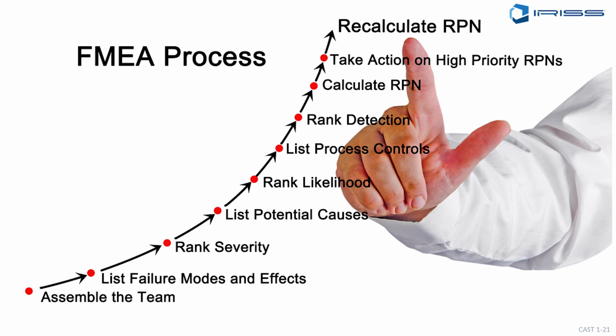What happens to my process or my facility if this asset fails? What gets affected downstream? Electrical infrastructure is a pyramid—the stuff at the top takes out everything below it. That piece of incoming medium voltage switchgear, or that main utility substation transformer, that 10 MVA or 50 MVA transformer—if it goes out, we are pooched. Everything downstream is out of operation.